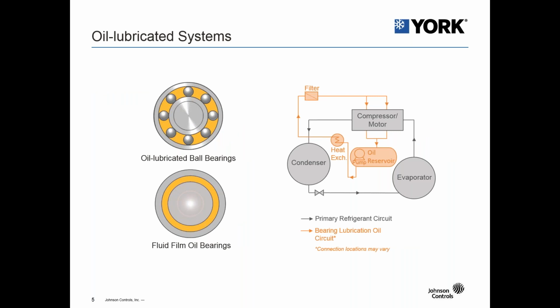So when we look at oil lubricated systems on a chiller package, looking at both the oil lubricated ball bearings and the fluid film oil bearings, which are used today in traditional applications that we've seen on chillers for decades, you'll see on the right-hand side a chiller schematic, and everything shown in the orange color is the bearing lubrication oil circuit. So required for these systems, you need a oil reservoir to hold the oil, the reserve oil, a pump, or you will need system pressure differential to move the oil, and then you also need a heat exchanger to control the temperature of the oil, and then finally a filter prior to the oil going back into the compressor motor assembly.